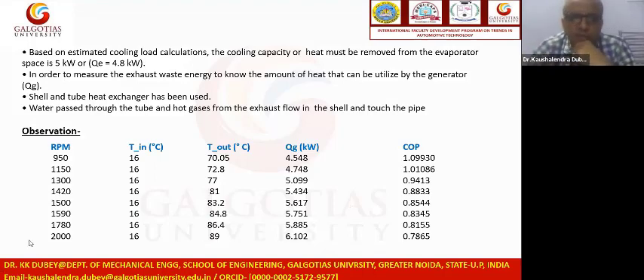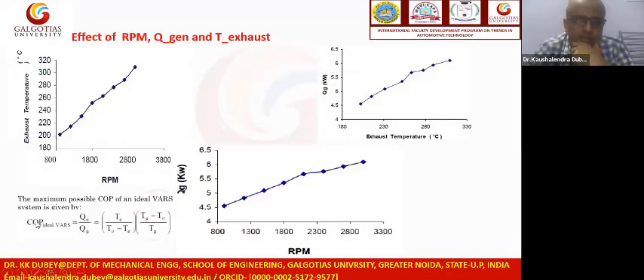So we can see in this result and observation that when we increase the RPM, we cannot achieve much COP. Although the recommended COP for the ammonia plant is about 0.3 to 0.5, here we are achieving 1.2, a very good COP for the cooling achievement. But if we increase the RPM, the exhaust temperature also increases and the Q generator increases, but we cannot achieve the COP. So here we can see the very simple thermal expression of the COP: Q cooling effect, Q evaporator, divided by the Q generator. The Q generator increases, so we cannot achieve the COP.